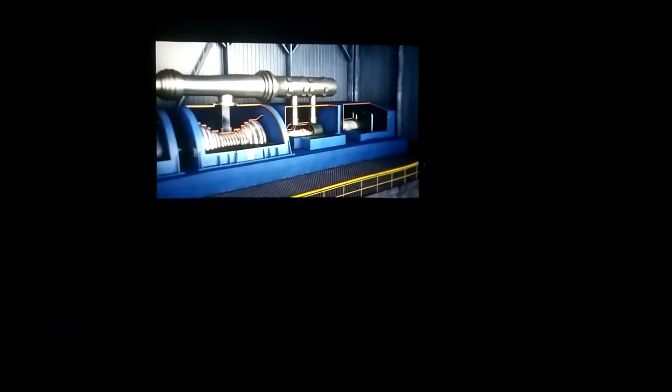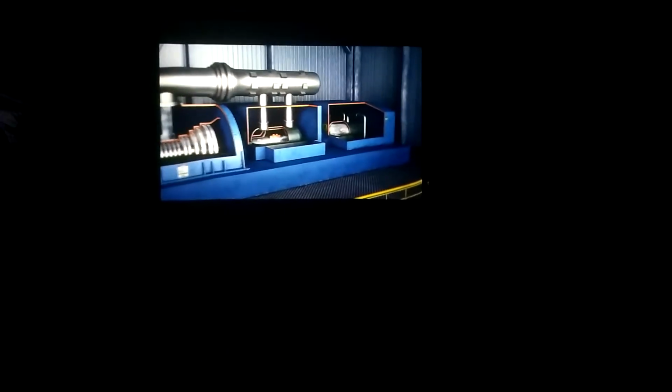Superheated steam from the boiler, which is approximately 2400 psi and 1000 degrees, travels to the high-pressure section of the turbine, where it creates the force that turns the turbine shaft. This process causes the steam to lose temperature and pressure, so it must be sent back to the boiler to be reheated to 1000 degrees. After reheating, the steam returns to the intermediate turbine and continues through the crossover into the low-pressure turbine.